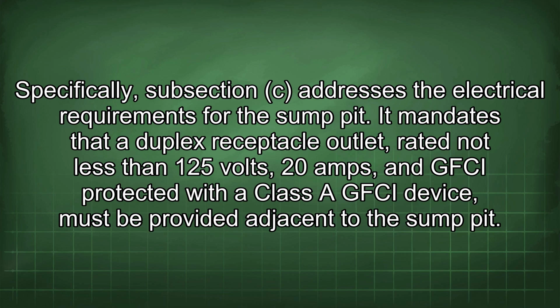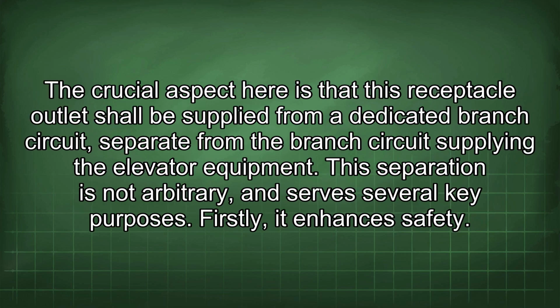It mandates that a duplex receptacle outlet, rated not less than 125 volts, 20 amps, and GFCI protected with a Class A GFCI device, must be provided adjacent to the sump pit. The crucial aspect here is that this receptacle outlet shall be supplied from a dedicated branch circuit, separate from the branch circuit supplying the elevator equipment. This separation is not arbitrary and serves several key purposes.